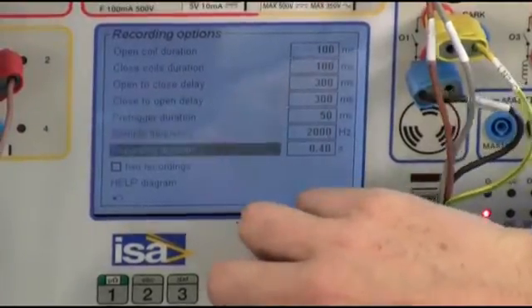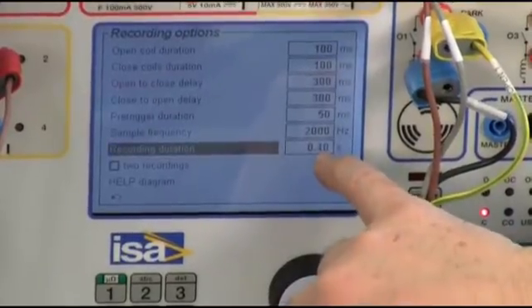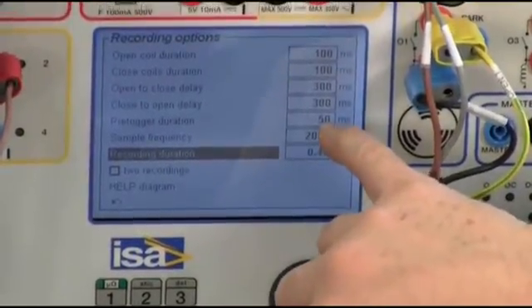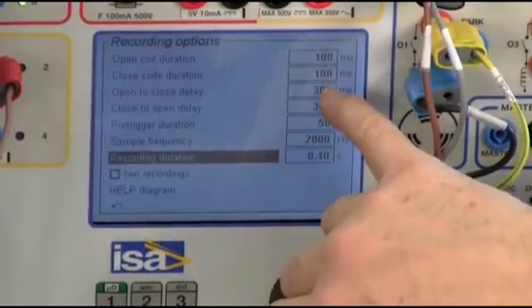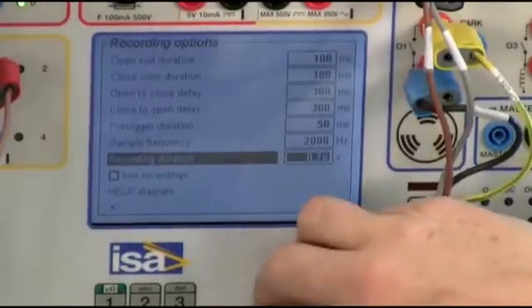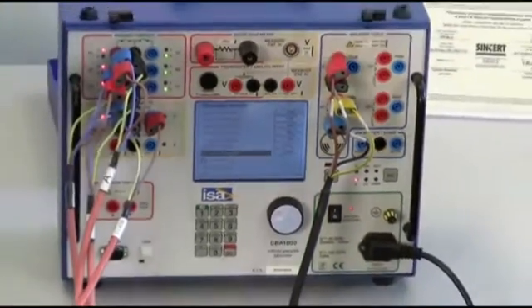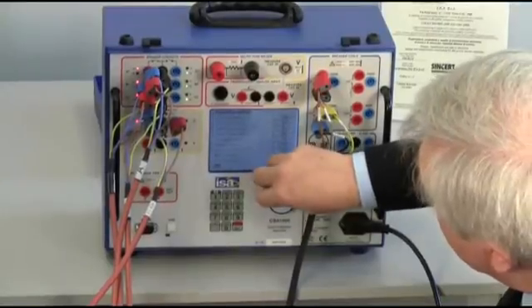Pre-trigger, okay, 50 milliseconds, 2 kilohertz, recording duration. This value is too short. Why? Because I have 50 milliseconds of pretrigger, then 300, then 300 is 600, 650. I program here 800 milliseconds, that is 0.8 seconds, so that the complete sequence is displayed on the screen.